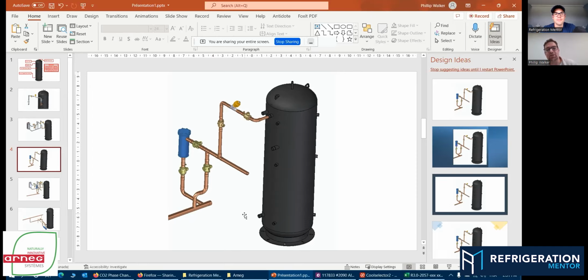This is a much larger system, regardless of all the measures that are put in place. These types of tanks are used, just to paint a picture, for systems that are 125 kilowatts or 167 horsepower, more or less. This is standard large scale supermarket design. Our minimum load we're going to see throughout the nighttime is 20 to 30%. So the medium temperature is always running. We got a lot of those great open display cases for meat or produce. So always a good amount of gas being produced, and then managing that pressure inside here to keep that stability.